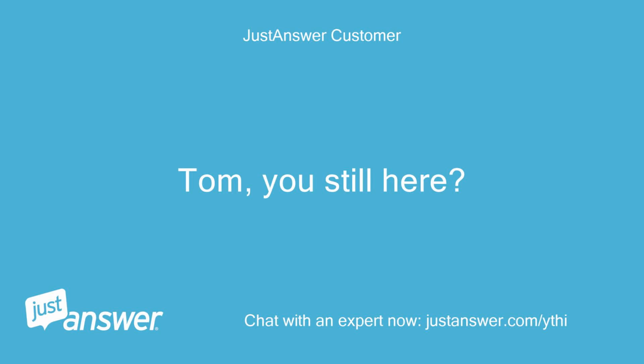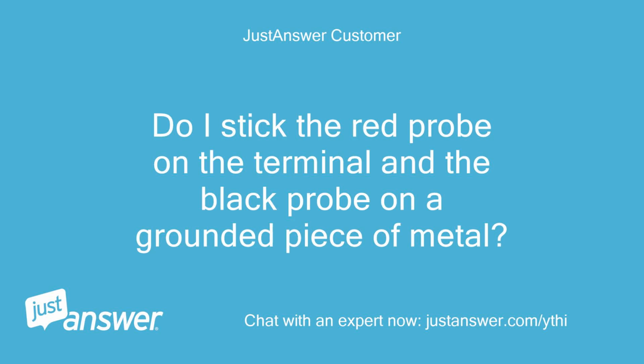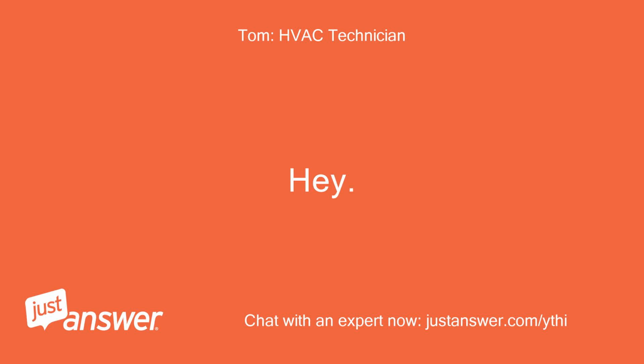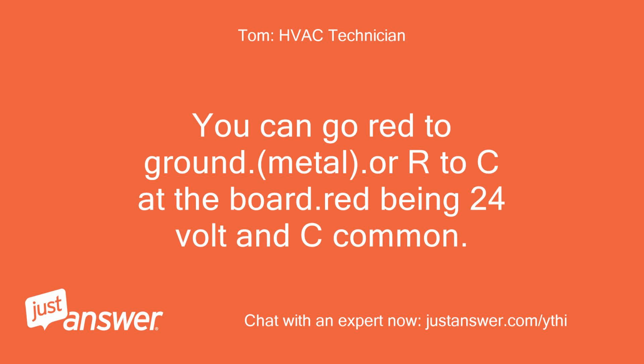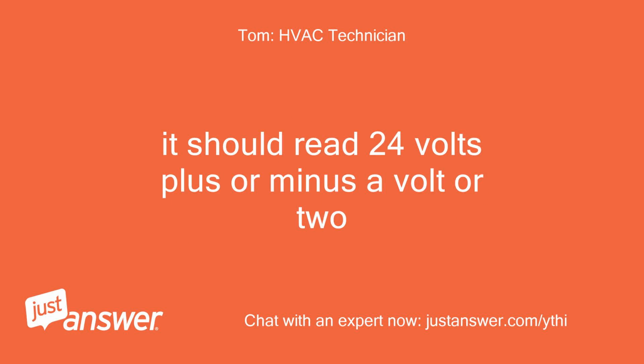Tom, you still here? I got the voltmeter. How do I use it? Do I stick the red probe on the terminal and the black probe on a grounded piece of metal? Hey. I'm here. You can go red to ground metal. Or R to C at the board. Red being 24 volt and C common. It should read 24 volts plus or minus a volt or two.